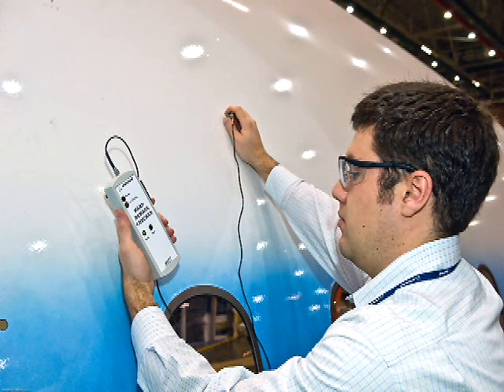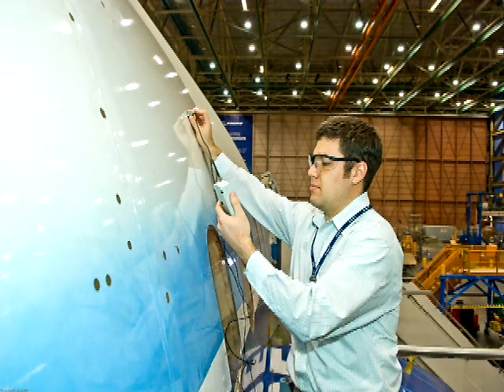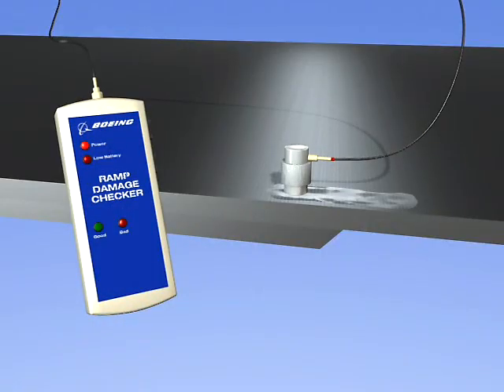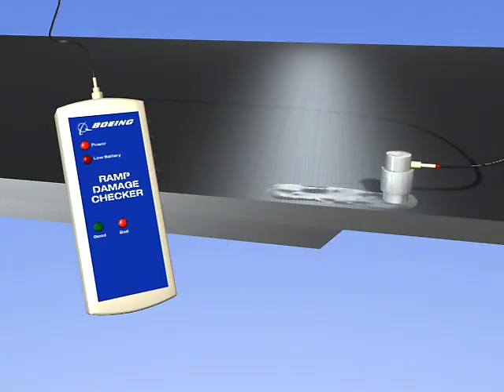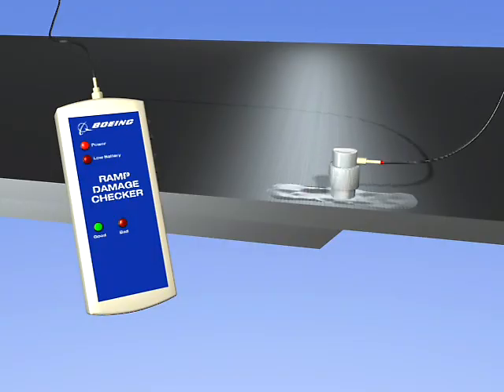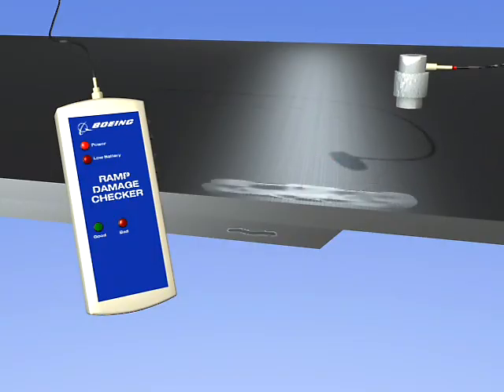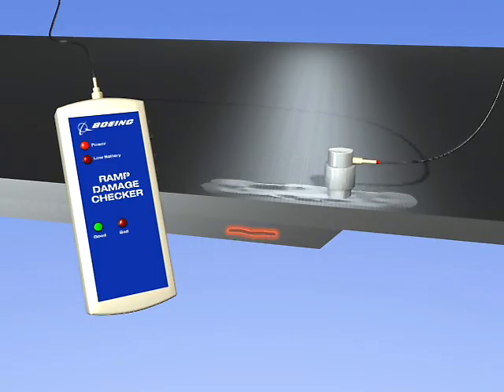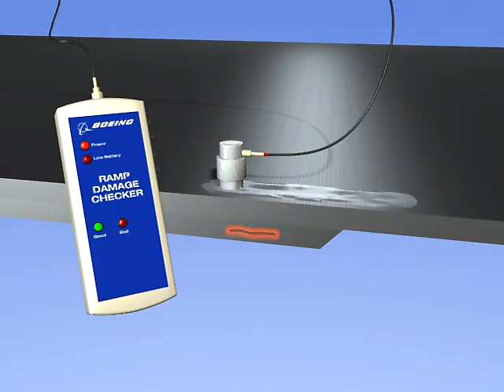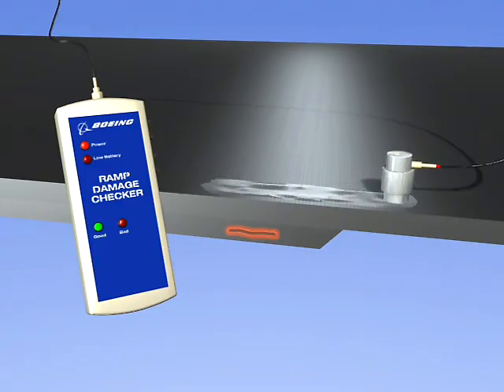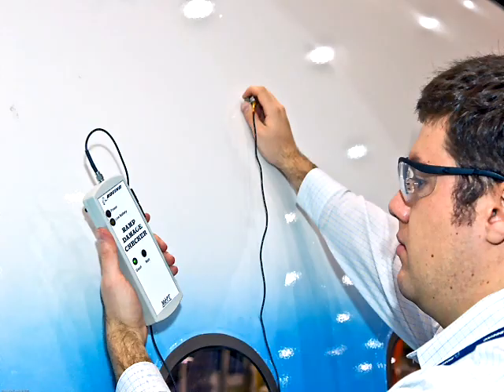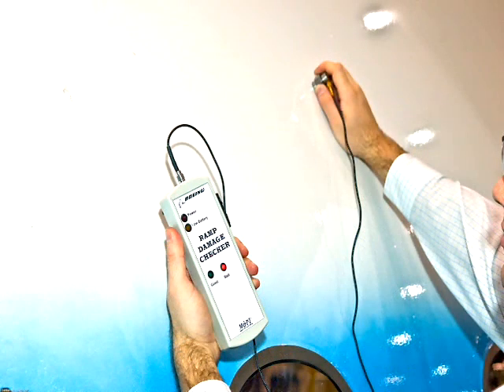Because the RDC does not distinguish between delaminations and thickness changes, the user must understand how the RDC thinks to complete the inspection accurately. If the user calibrates the RDC in a thick area and then moves to a thinner area, the bad light will illuminate. This is because the signal takes less time to return to the probe, and the RDC interprets the early reflection as a defect. If the user calibrates the RDC in a thin area and then moves to a thicker area, the RDC will not identify defects that occur beyond the calibration thickness, because it only monitors signals that return earlier in time than the calibration signal. This is why it is imperative that the user know where these thickness changes occur.